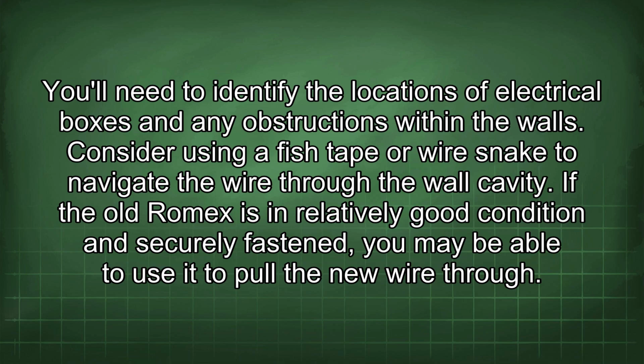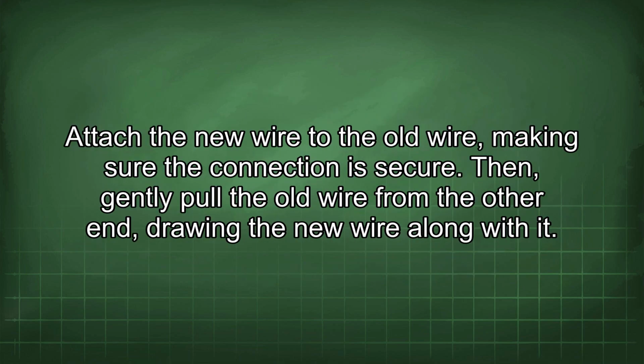If the old Romex is in relatively good condition and securely fastened, you may be able to use it to pull the new wire through. Attach the new wire to the old wire, making sure the connection is secure. Then, gently pull the old wire from the other end, drawing the new wire along with it.